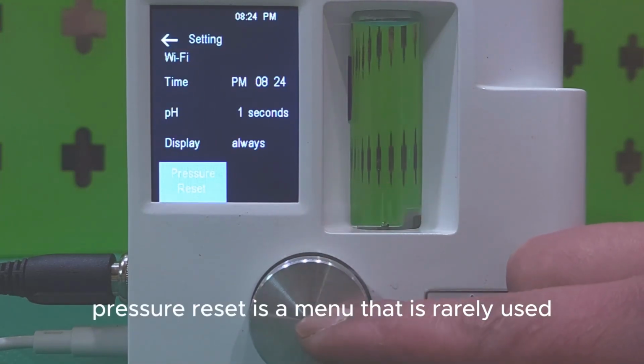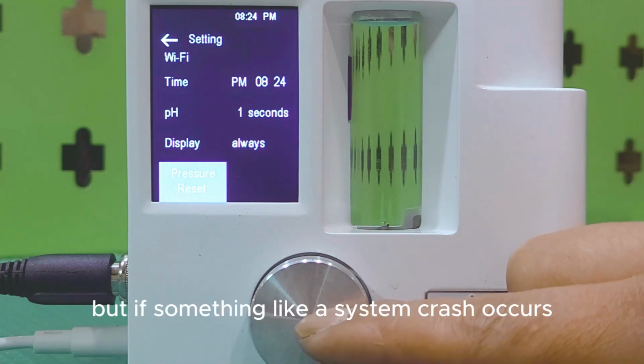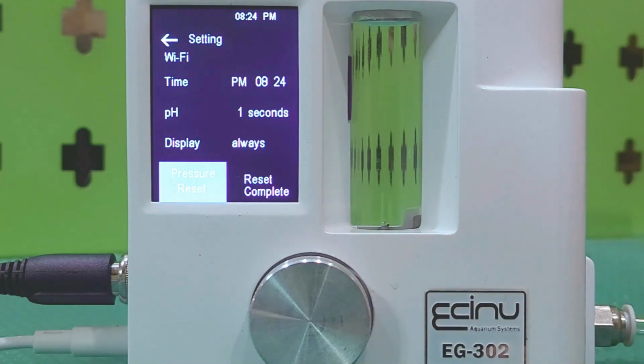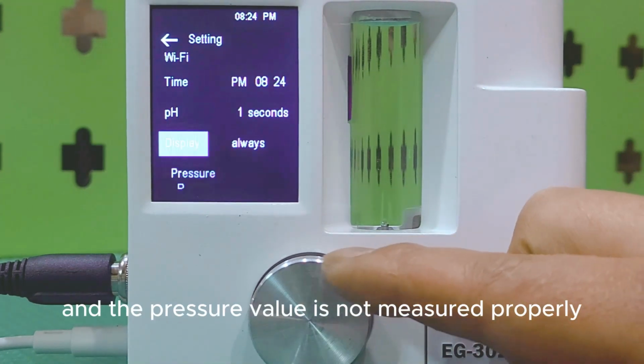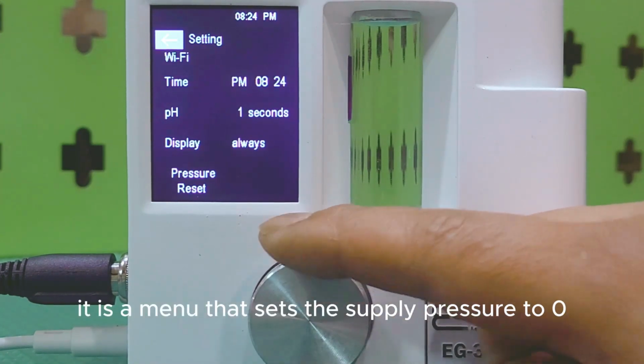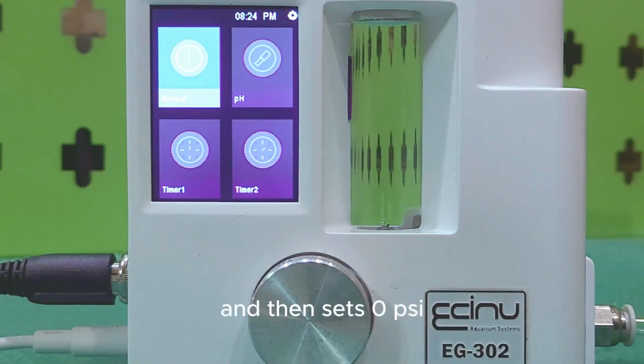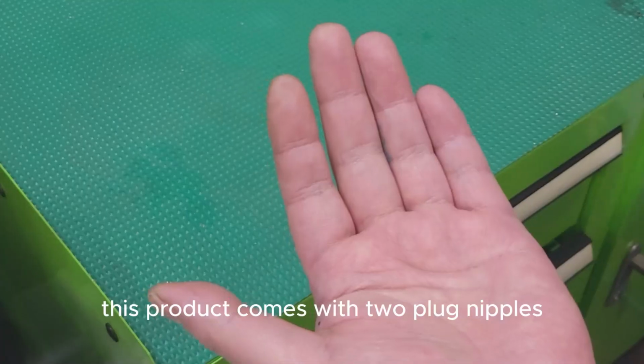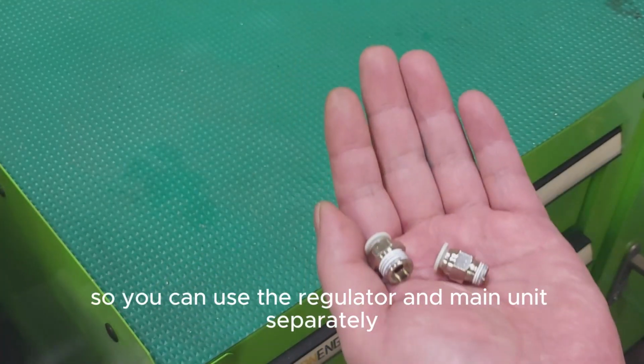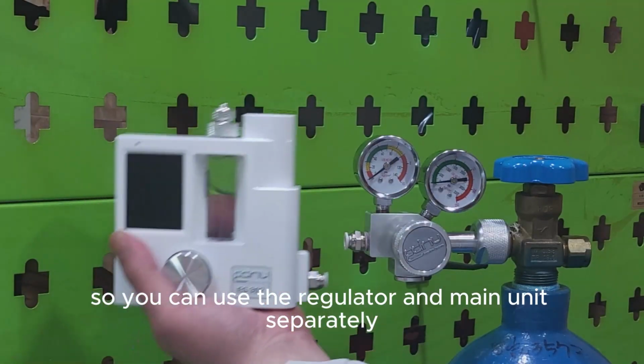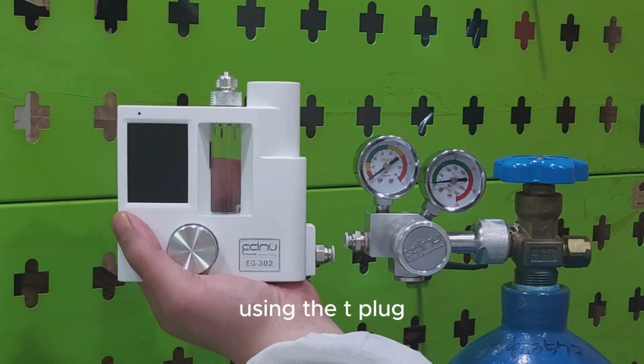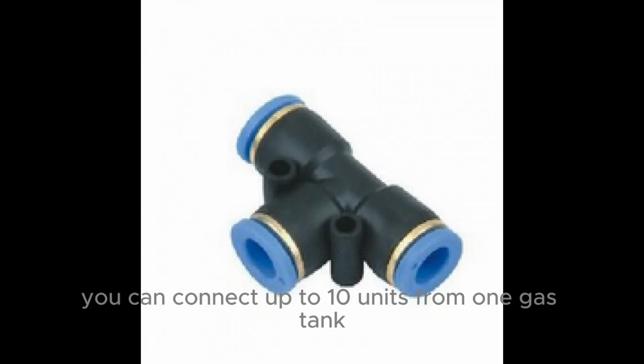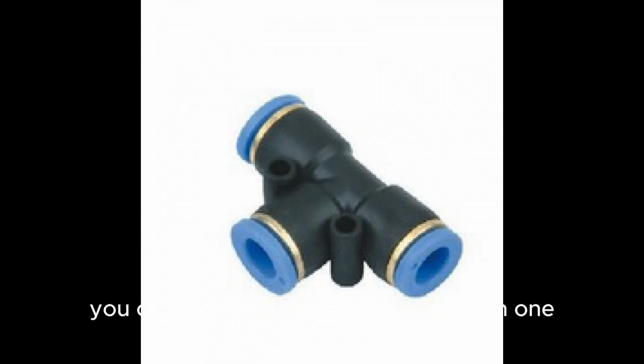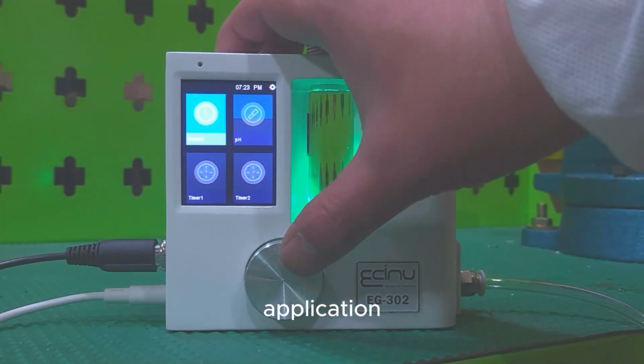Pressure reset is a menu that is rarely used, but if something like a system crash occurs and the pressure value is not measured properly, it is a menu that sets the supply pressure to 0 and then sets 0 psi. This product comes with 2 plug nipples, so you can use the regulator and main unit separately in this way. Using the T-plug, you can connect up to 10 units from one gas tank. You can also control up to 10 units with one application.